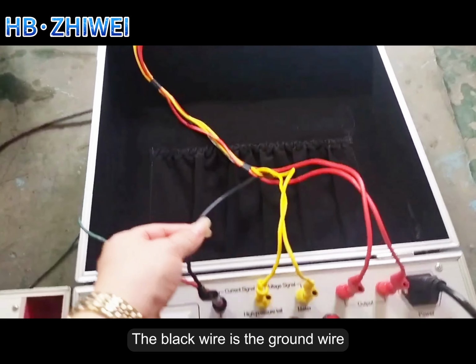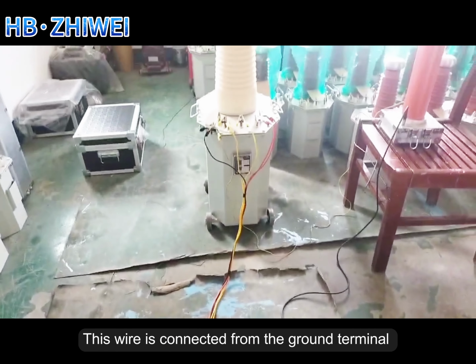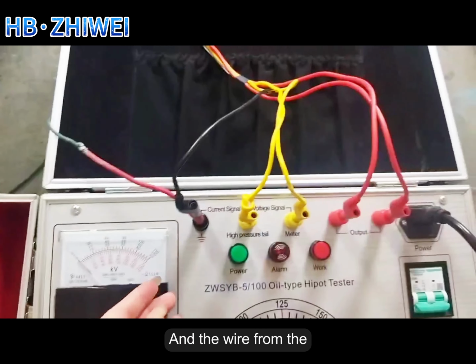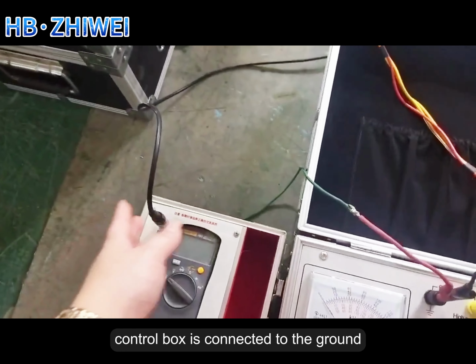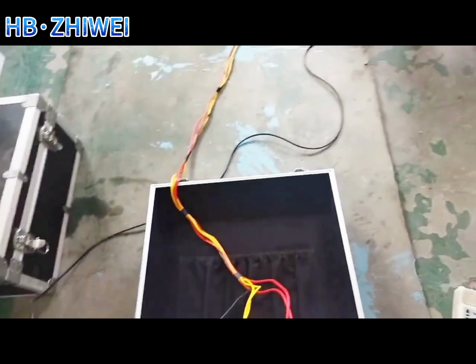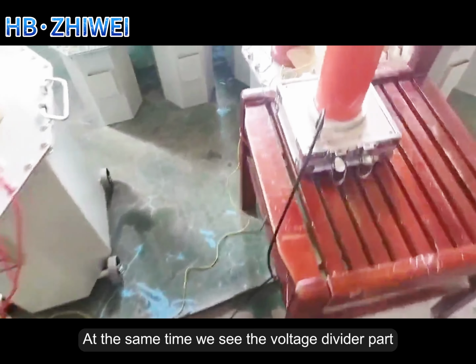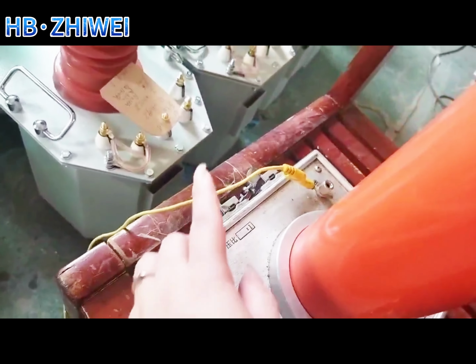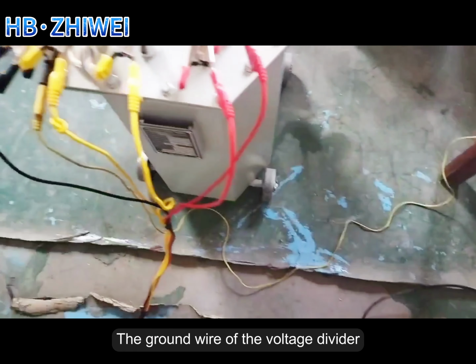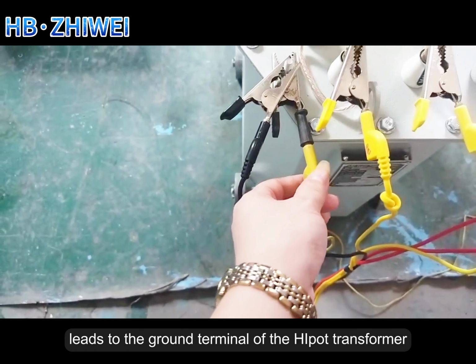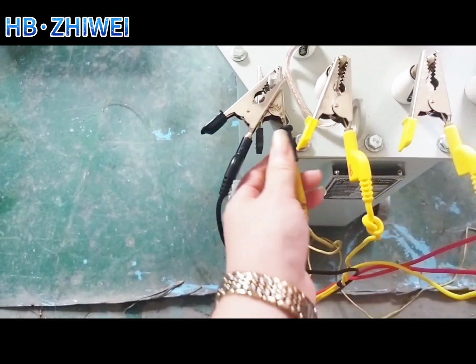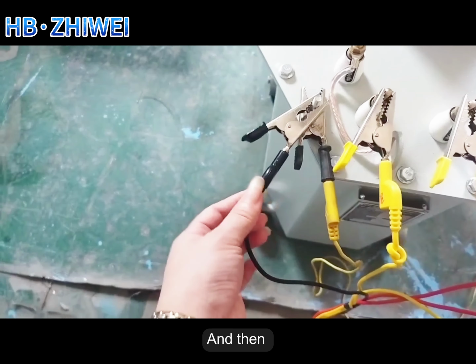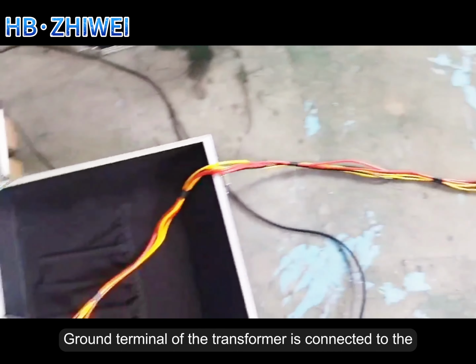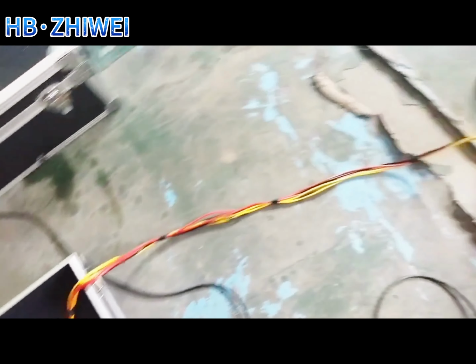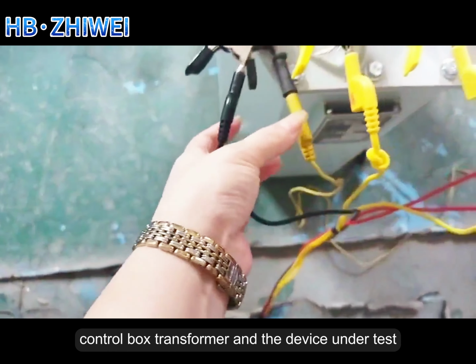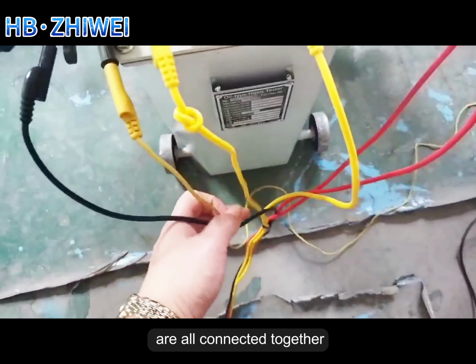The black wire is the ground wire. This wire is connected from the ground terminal of the Hipot transformer, and the wire from the control box is connected to the ground. At the same time, we see the voltage divider part. The ground wire of the voltage divider leads to the ground terminal of the Hipot transformer, and then the ground terminal of the transformer is connected to the ground terminal of the control box. The ground wires of the control box, transformer, and the device under test are all connected together.